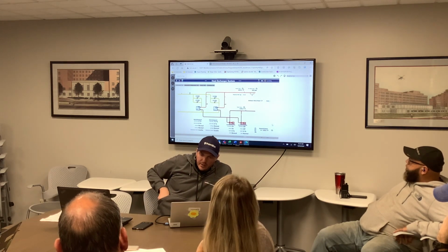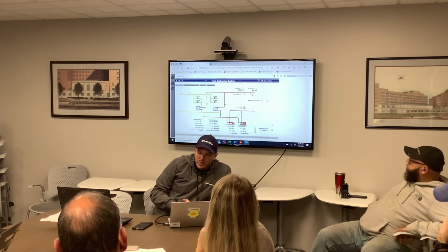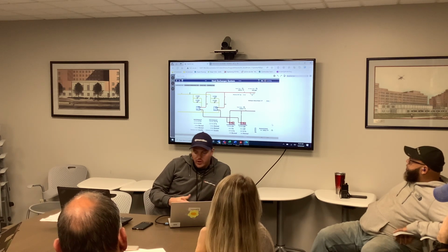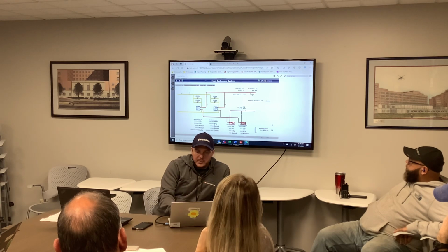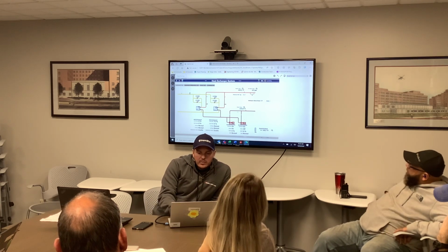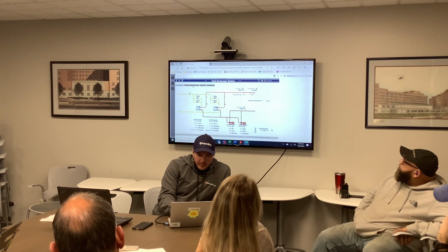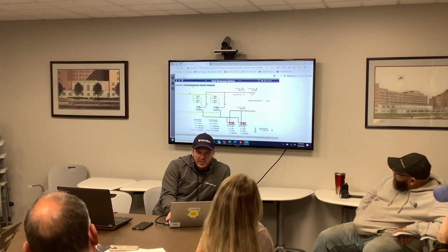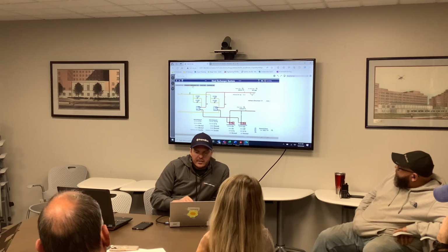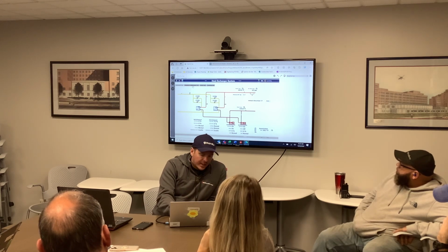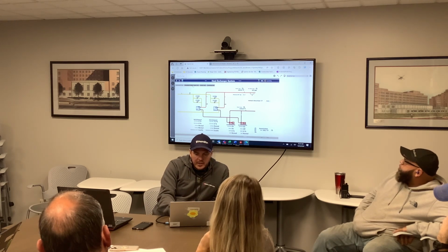So there it cleared, and then it would go back into normal operation. If it goes back into alarm, you know you have something up. They were both commanded on, and then the alarm commanded it off. Right now, one of these pumps is in hand. I didn't release them before I came over, so I'll get to the bottom of that.